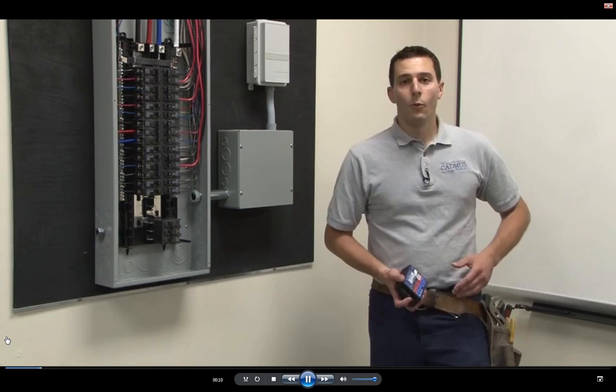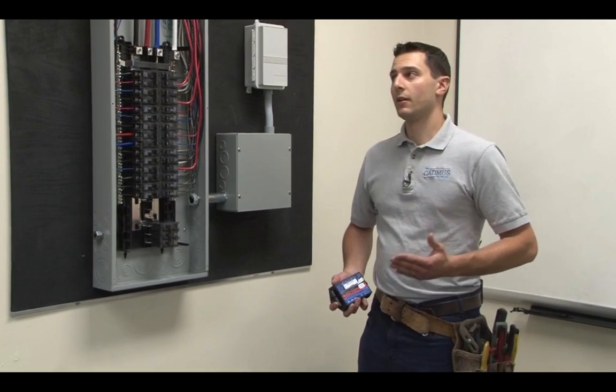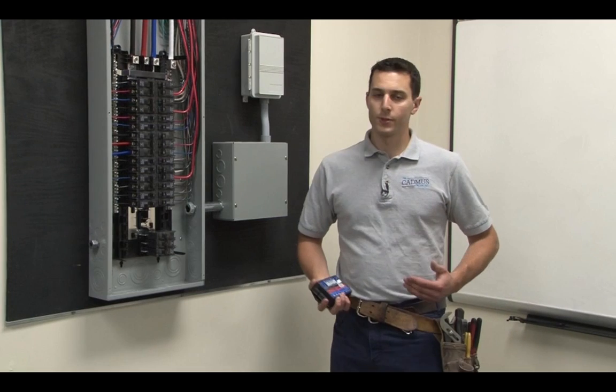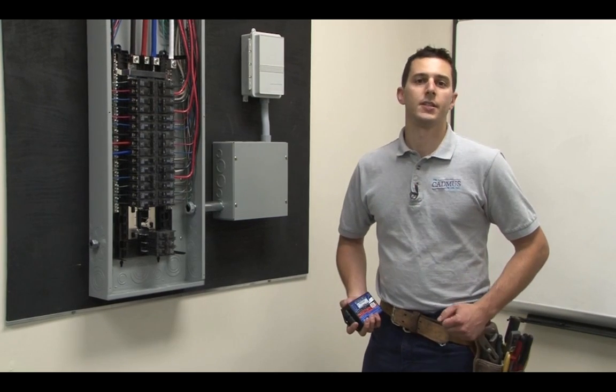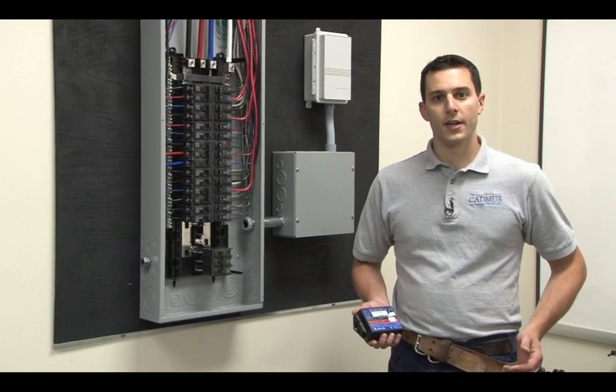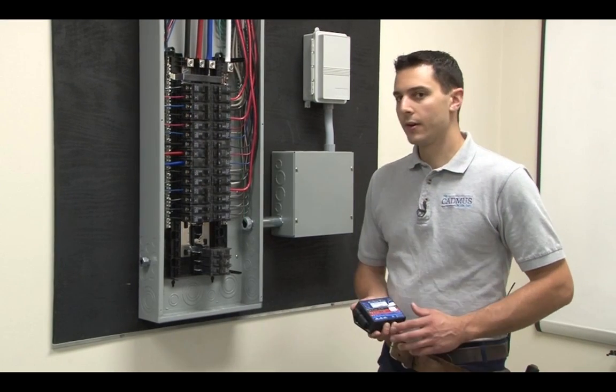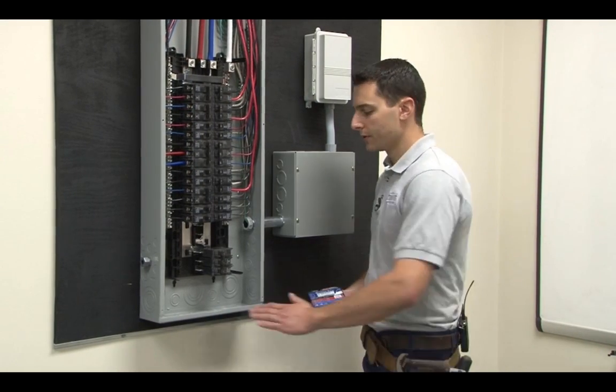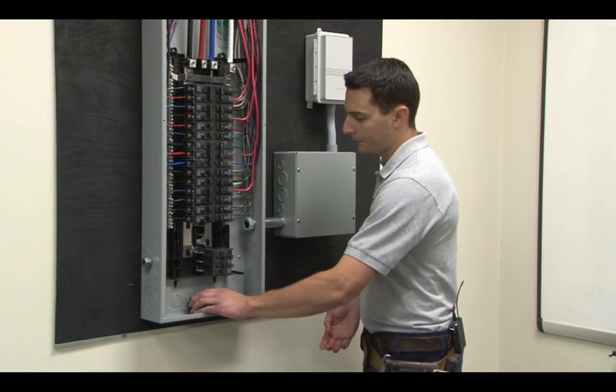Single circuit using a Wattnode and a HOBO U30. Once again, we'll be doing this on our display panel board, which is de-energized, so we can focus on the equipment installation. If this was a live panel board, I'd be wearing the necessary safety gear. We'll start out by identifying a safe location for our Wattnode. For this installation, we'll use the bottom of this panel board right here.